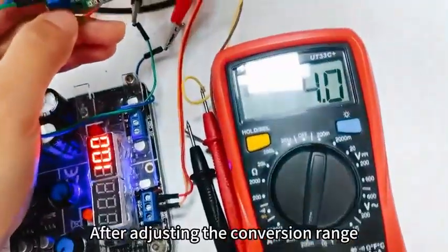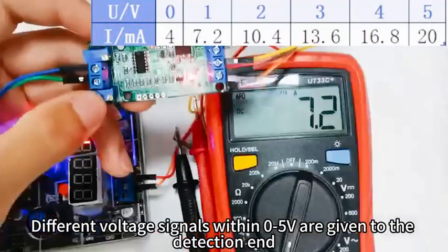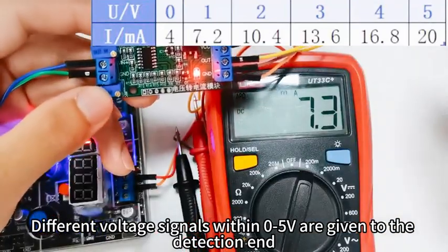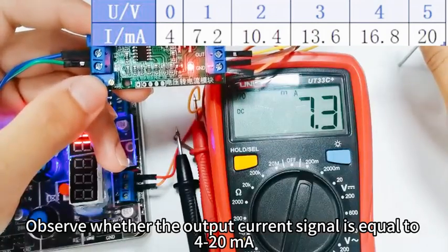After adjusting the conversion range, Step 7: Different voltage signals within 0 to 5 volts are given to the detection end. Observe whether the output current signal is equal to 4 to 20mA.